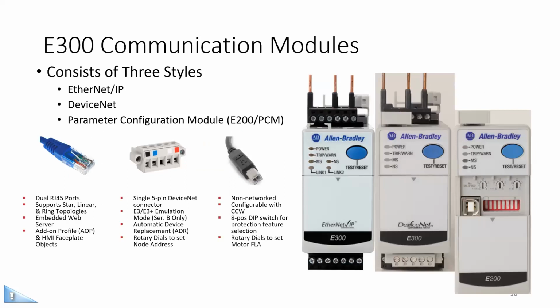The third module is a communication module. There are 3 different styles of those. There's the Ethernet IP, there's the device net, and a parameter configuration module. It's going to be this far right one. You notice on the bottom it says E200. So with the E200, you get this parameter configuration module. So USB-B plug-in. You can configure it that way for Ethernet or device net.